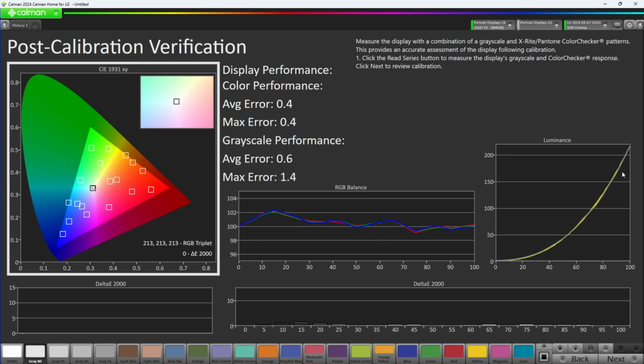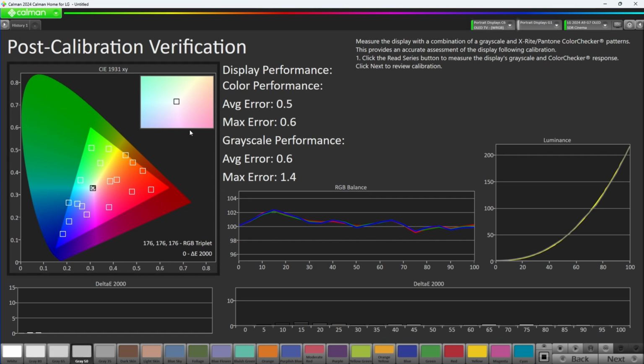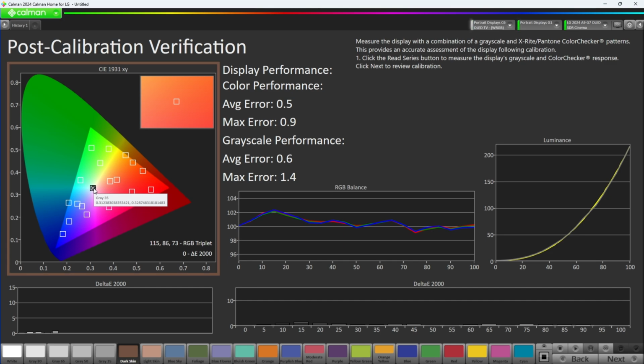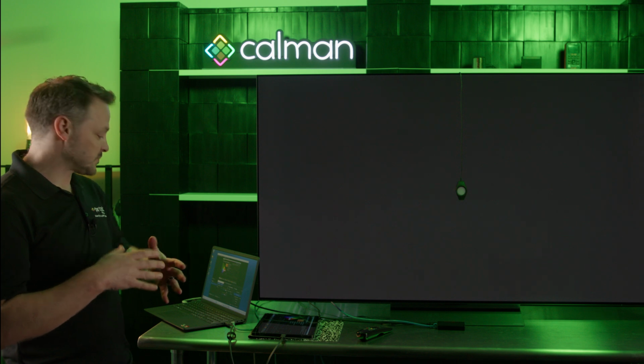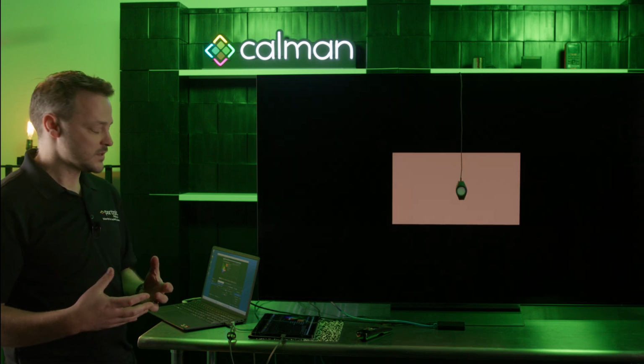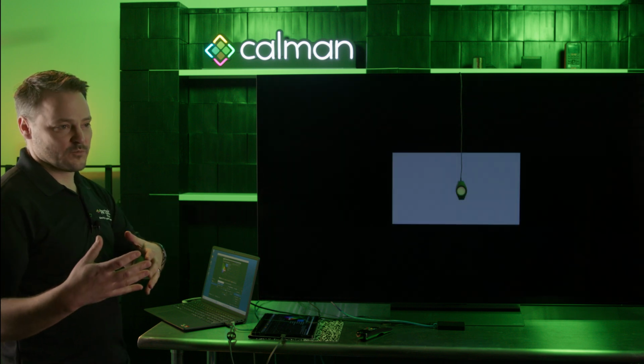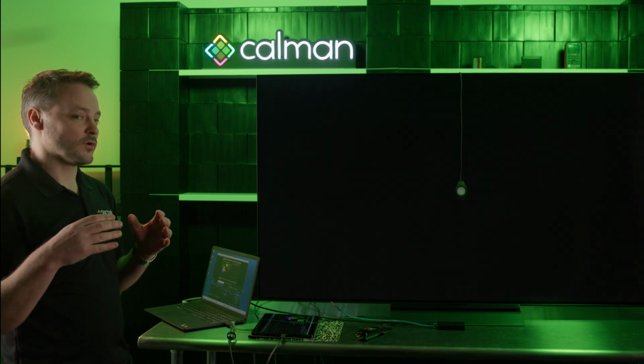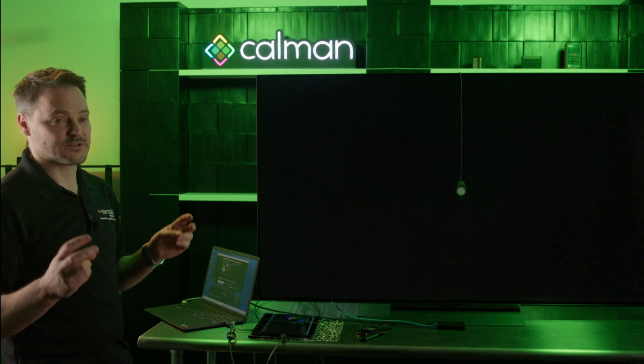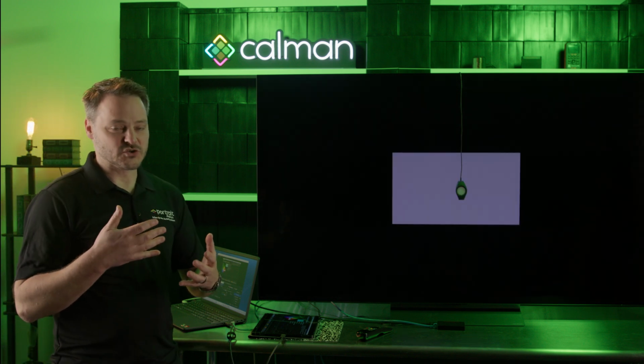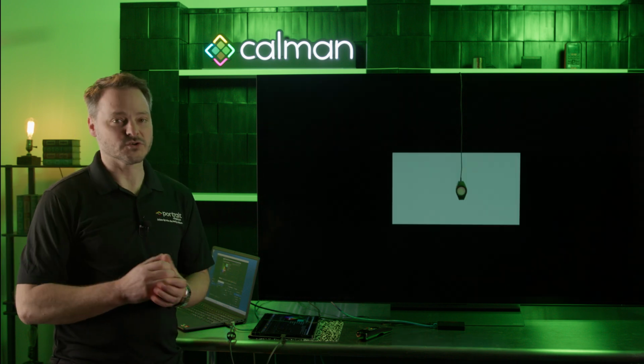As we go into the color checker, you'll notice that with each measurement that we're taking, the circles are the measured data, the boxes represent our targets, and the circles are lining up very closely in the target boxes. Obviously, a lot of these points are points that we didn't calibrate at specifically. So what that means is we're measuring at different points than we calibrated, so we're seeing what the calibration overall looks like, even for points that we didn't necessarily touch while we were calibrating, which is nice because that way we can make sure that the calibration applies for all of the picture content that we're going to see. As such, we'll expect some of those to not be necessarily a perfect DE of 0.5 or lower, but we expect them to all look still pretty good.